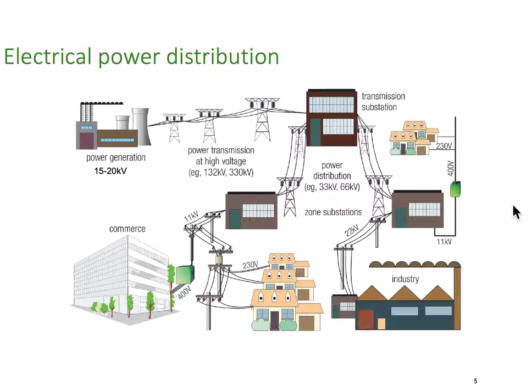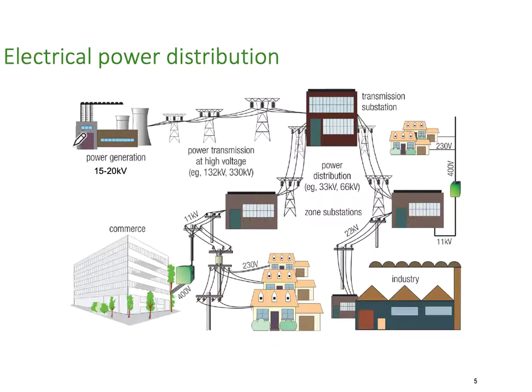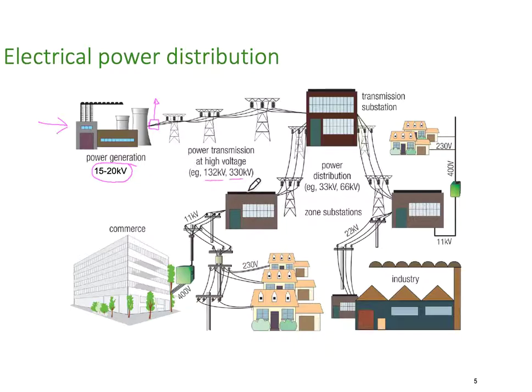Let's have a close look at this electric power distribution diagram. We're going to start over here with generators. Generators could be coal-fired steam generators, solar, hydro, or wind — there are lots of ways to generate electricity. Typically, those generating plants generate at about 15,000 to 20,000 volts. As they come out of the generation plant, they have a step-up transformer, stepping the voltage up to 132 kV or quite often 330 kV, and we transmit it through those large towers across the landscape to large distribution substations.